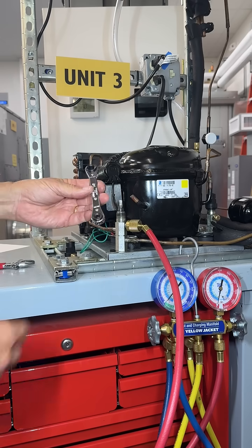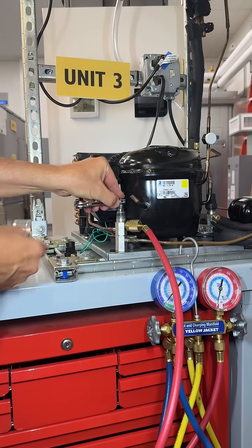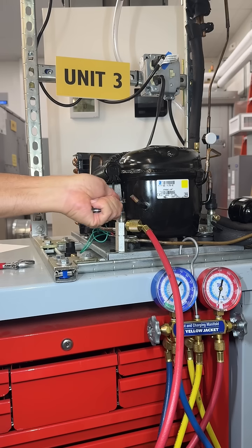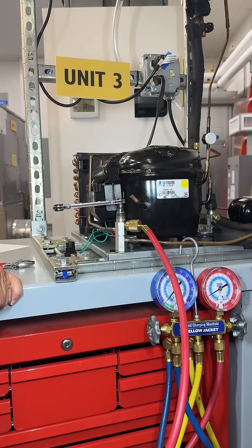Next, I'm going to use my service wrench, going to find the right size for that, put it on my service valve, and now I'm going to turn the service valve stem counterclockwise off the back seat, probably like a half a turn, nothing more than that.